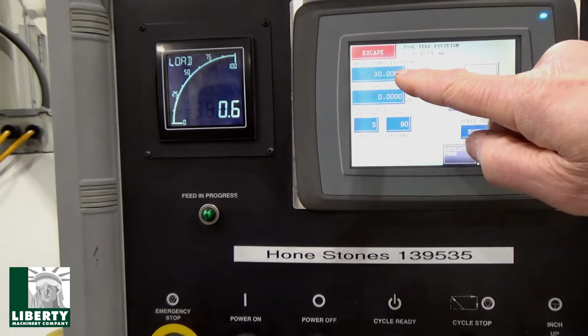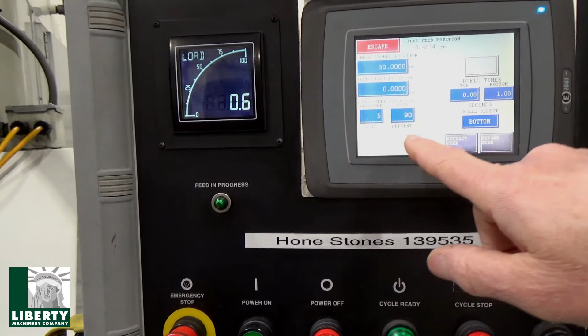There's check stones position, which gives you an alarm when it's time to check your stones because they're worn out. That's all settable, along with rough feed pressure and rate, set to 5 and 90. A lot of these numbers appear on multiple pages. There's also automation, which is there but turned off, so I won't go into it.